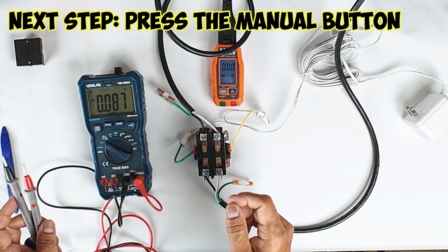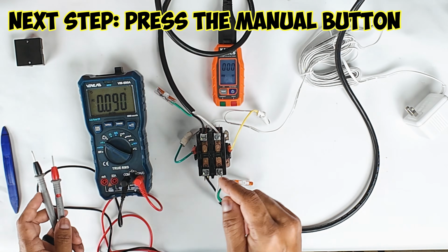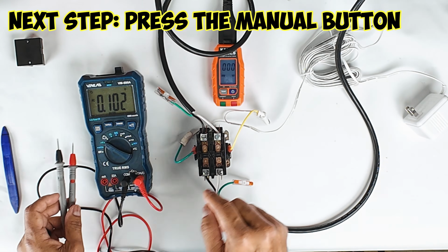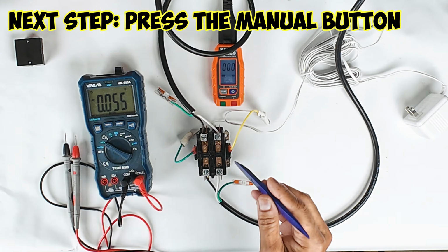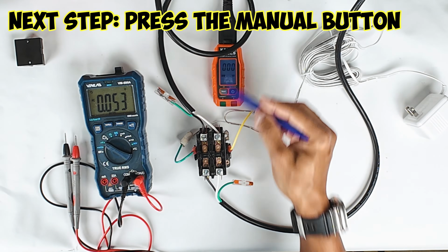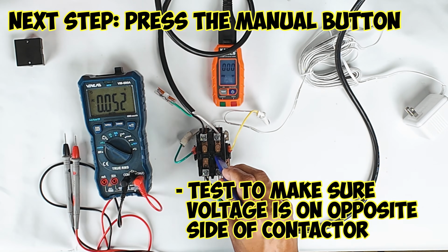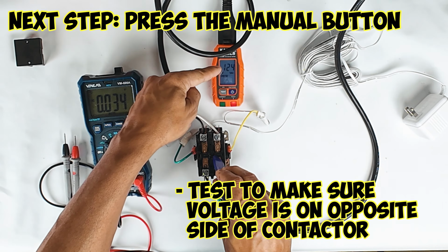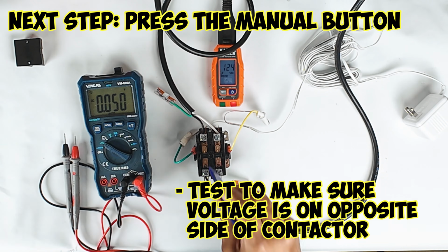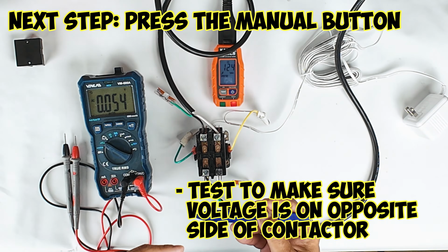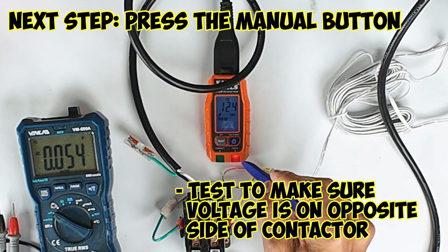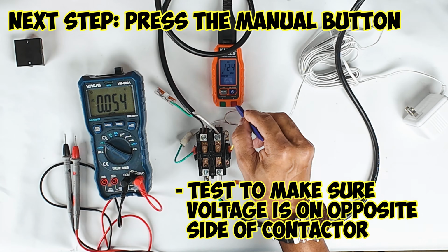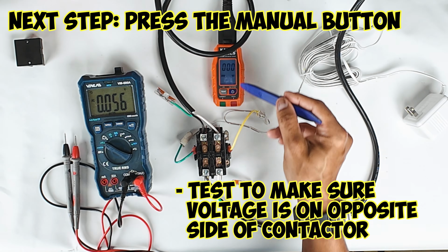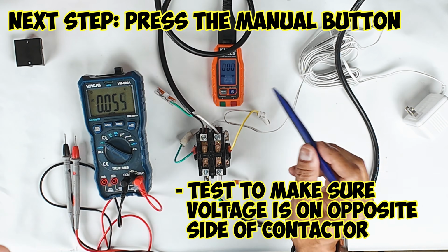The next thing you want to do is manually press in the button on your contactor and make sure that it sends voltage across the coils. If you press on it here, you can see on my meter, it sends 120 volts. If I release it, it's going to go back to 0. My meter here holds it for a little while, but eventually it starts flashing, which means it has actually lost connection. As you can see, the voltage is 0.